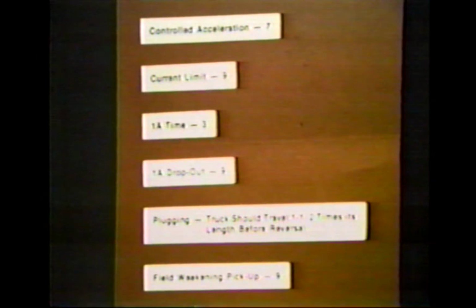The creep pot should be set so that the drive wheels begin to rotate when MS1 is closed. Control acceleration should be set on the number 7. Current limit on 9, 1A time on 3, and 1A dropout on 9. The plugging should be set so that the truck travels a minimum of 1 1/2 times its length before reversal when the truck is plugged. The field weakening pickup and dropout should be set on 9.